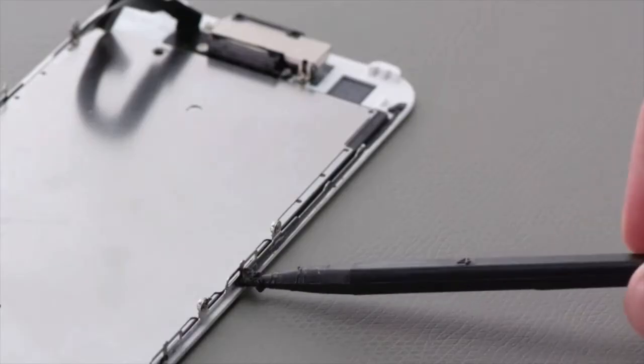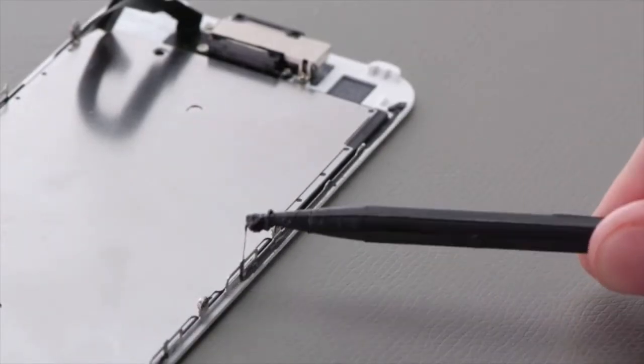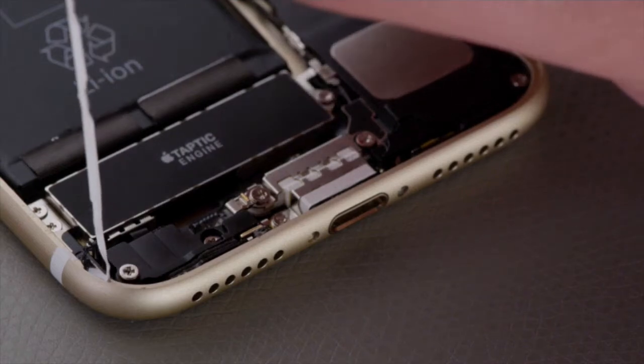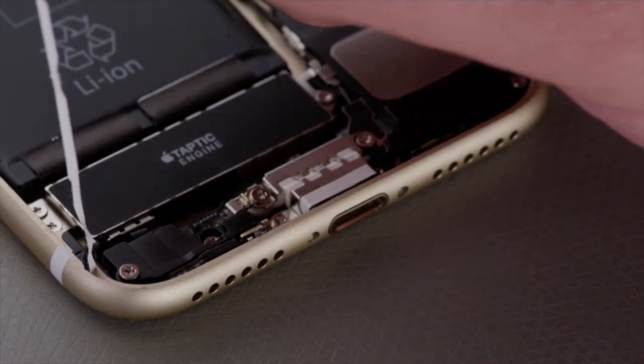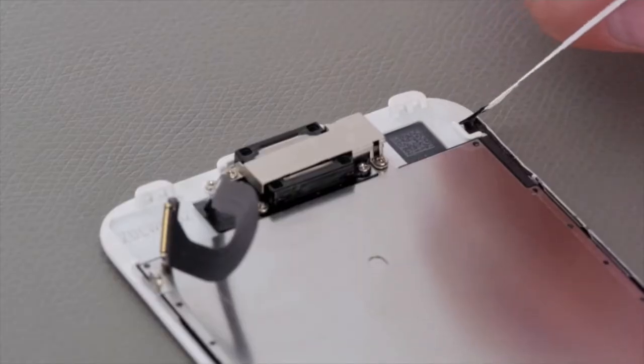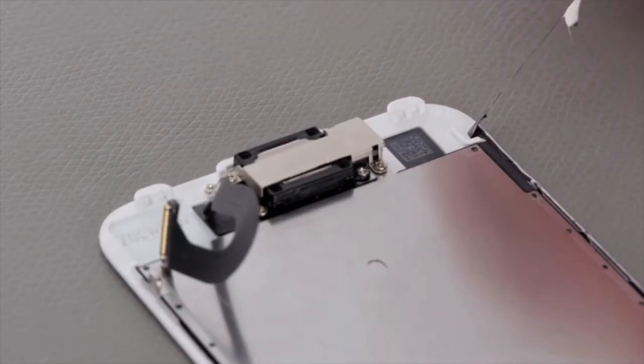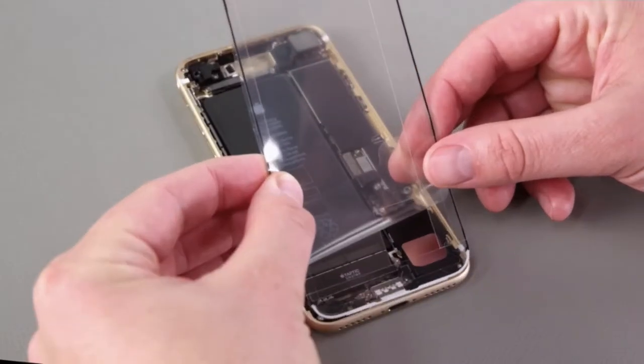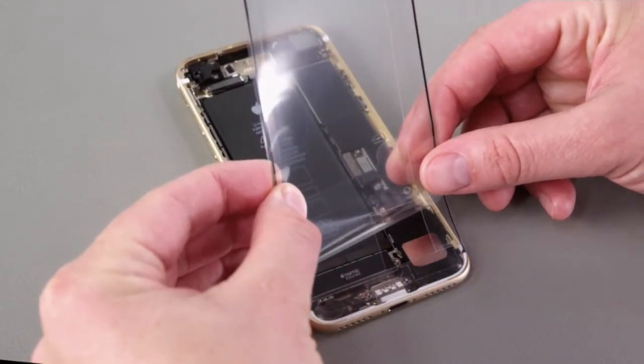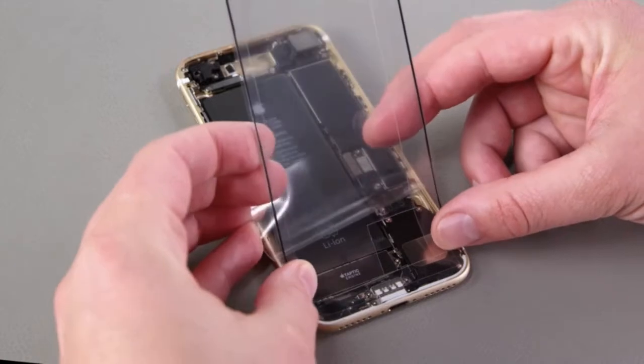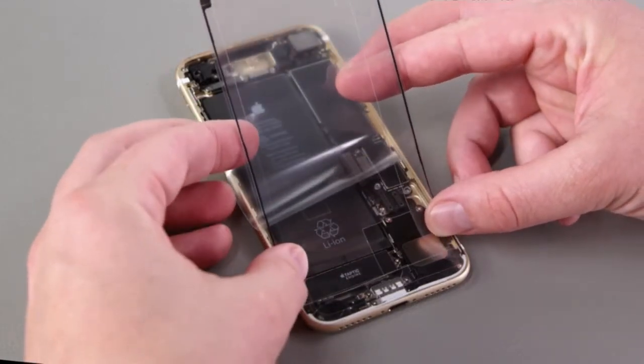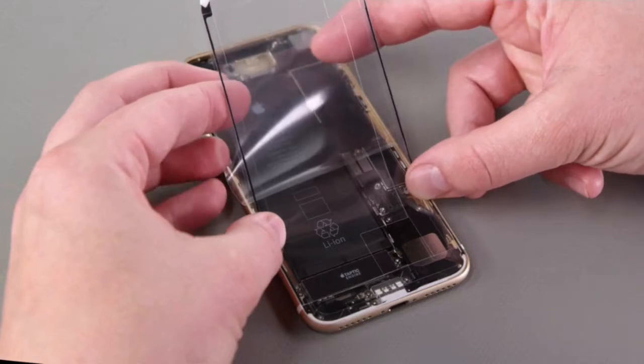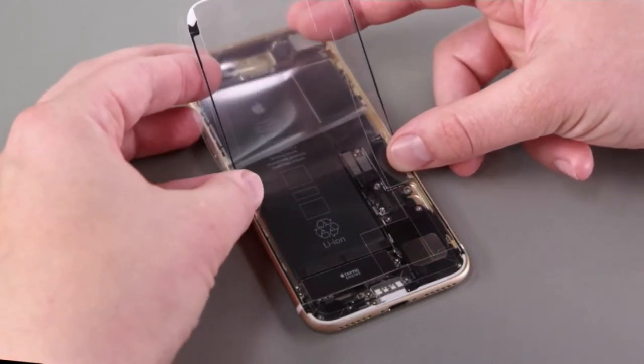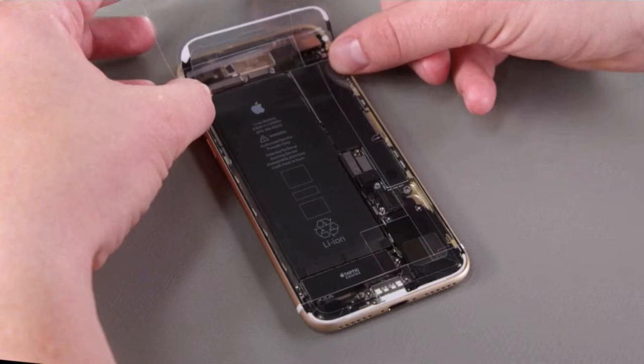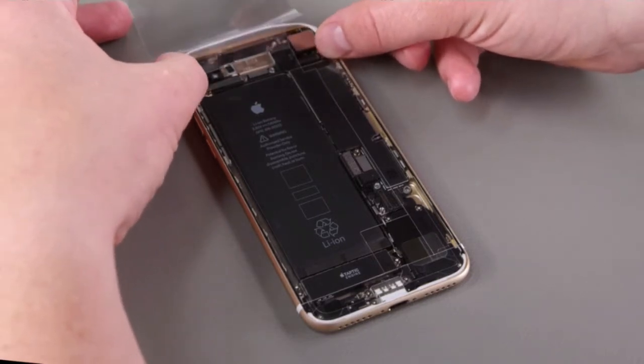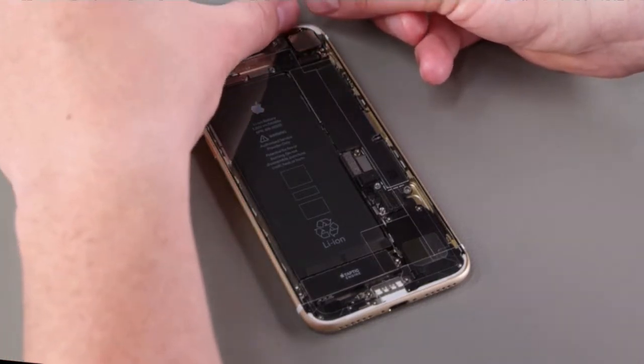Use a black stick to remove the adhesive around the display and enclosure. Clean the enclosure and display thoroughly to ensure a proper seal during reassembly. With the tab on the bottom right, align the display adhesive with the enclosure. Starting at the bottom edge of the enclosure, slowly remove the bottom release liner while pressing the adhesive into the enclosure. If the adhesive is not properly aligned, remove it and repeat the process with a new display adhesive.